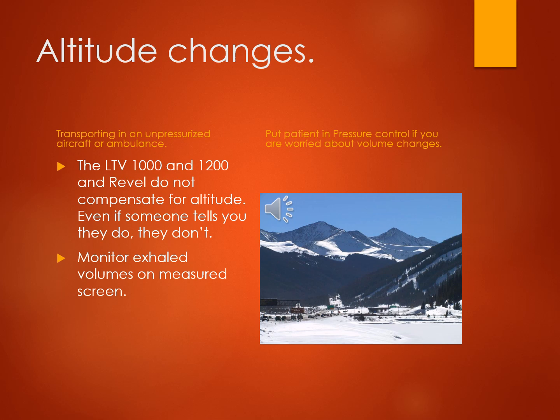So the LTV and the 1200 and Revel, they're not altitude compensated. There are ventilators out there that will say that they're altitude compensated if it's dialed in. So if that's the case, then you would have to dial that in to the ventilator and pay very close attention to that. Remember, when you're coming back down in elevation, you'd have to adjust it again. There are other ventilators out there like the Hamilton, the Eagle, Eagle Impact, a couple other transport ventilators that will have altitude compensation. That's great, and you don't have to worry about it.